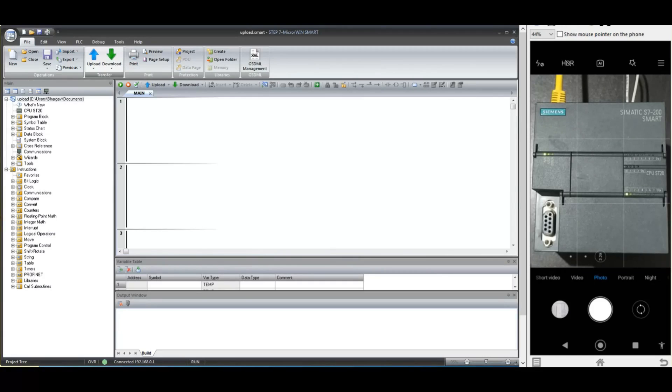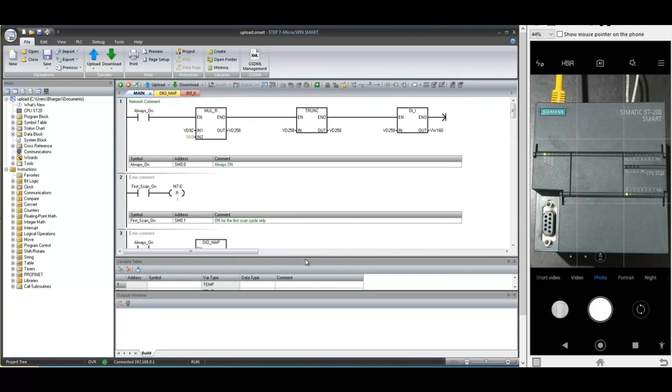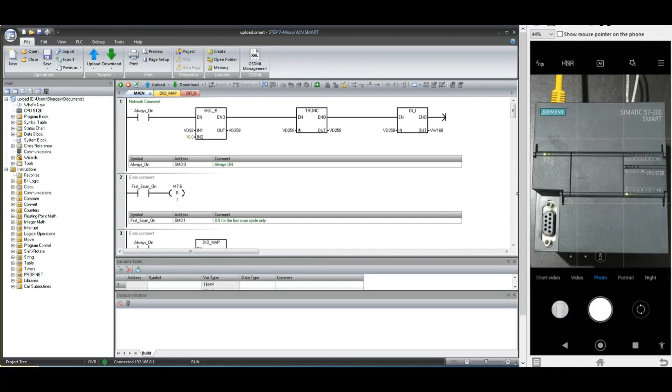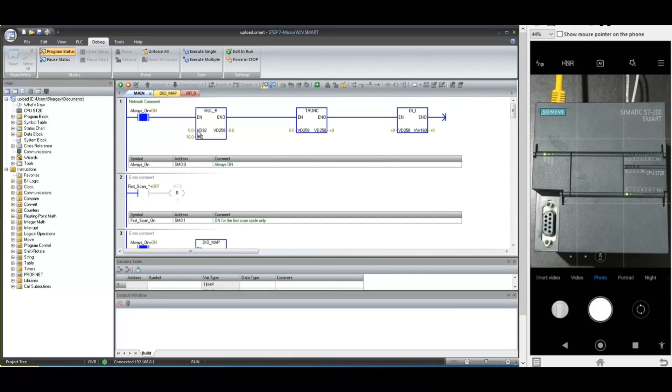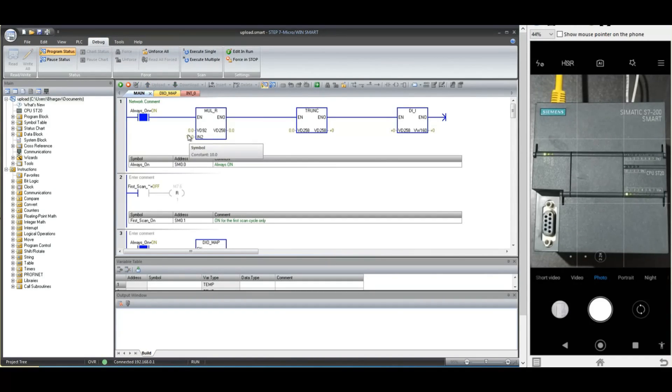Uploaded successfully. Now let us check the program by going online from the debug menu. Notice here, in this uploaded program, there are no tag names and no comments available. You will have only addresses in the uploaded backup.